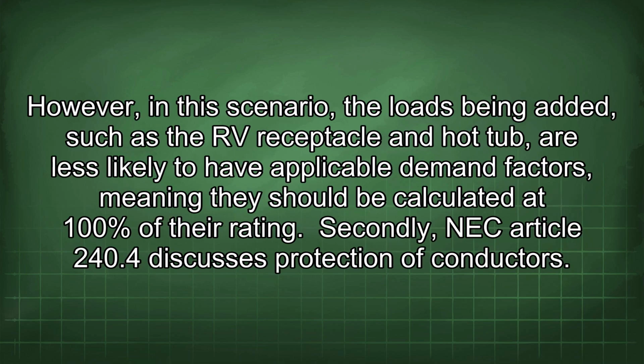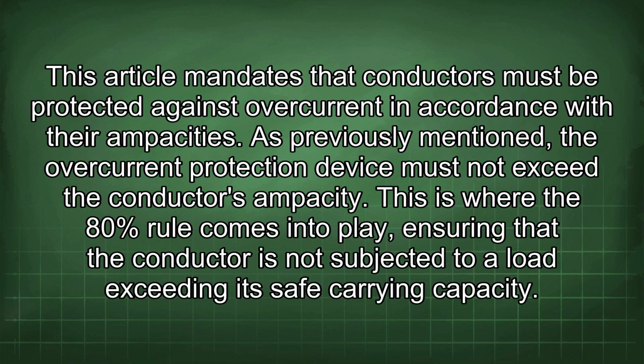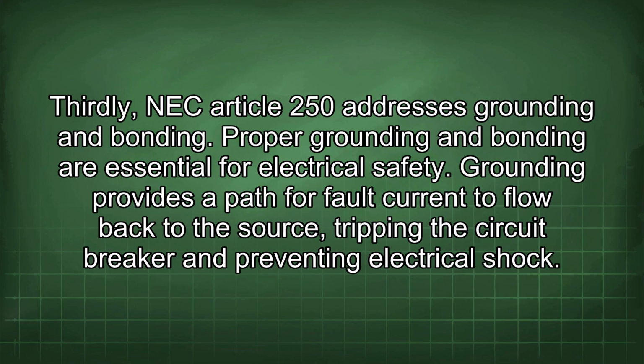However, in this scenario, the loads being added, such as the RV receptacle and hot tub, are less likely to have applicable demand factors, meaning they should be calculated at 100% of their rating. Secondly, NEC Article 240.4 discusses protection of conductors. This article mandates that conductors must be protected against overcurrent in accordance with their ampacities. As previously mentioned, the overcurrent protection device must not exceed the conductor's ampacity. This is where the 80% rule comes into play, ensuring that the conductor is not subjected to a load exceeding its safe carrying capacity. Thirdly, NEC Article 250 addresses grounding and bonding.